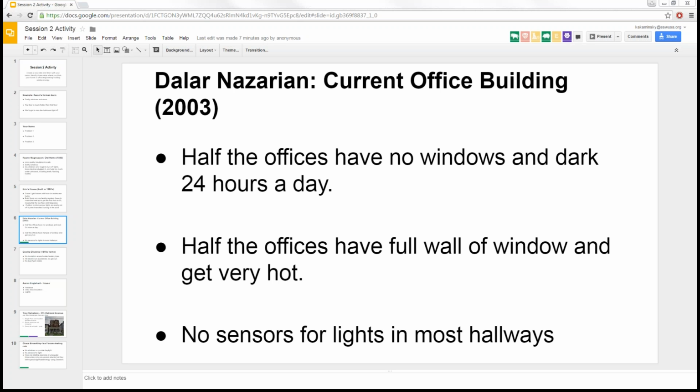And the other big problem is that some of the floors are basement floors, and even though they have no natural lighting, they have no light sensors either. So a lot of the lights end up being turned on all day long, even though no one's using the computer labs or the bathrooms, and it's a pretty large building with the lights on all of the time.